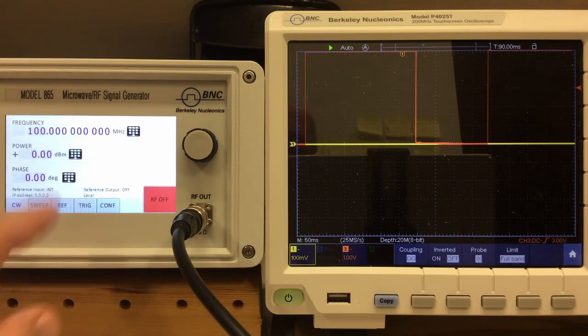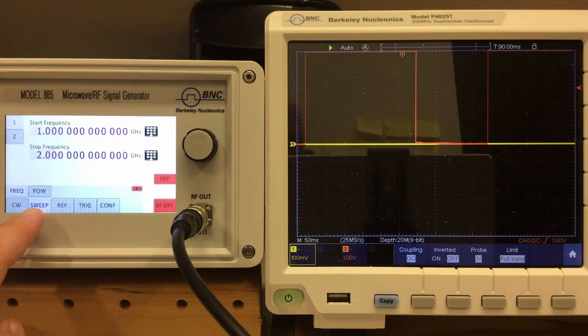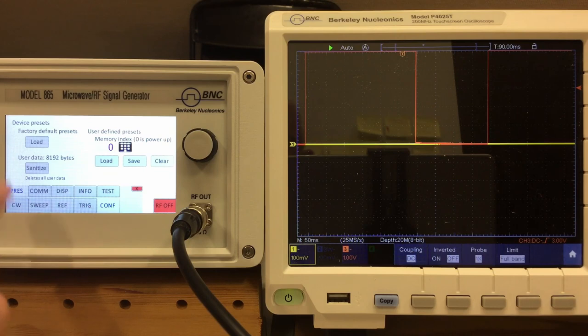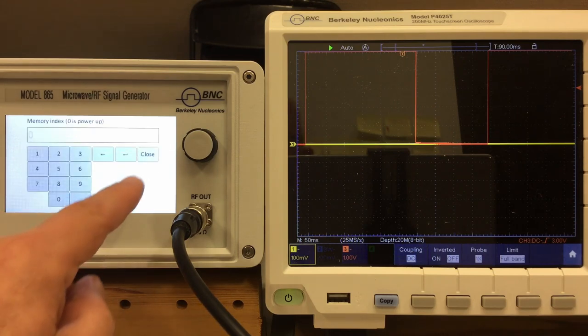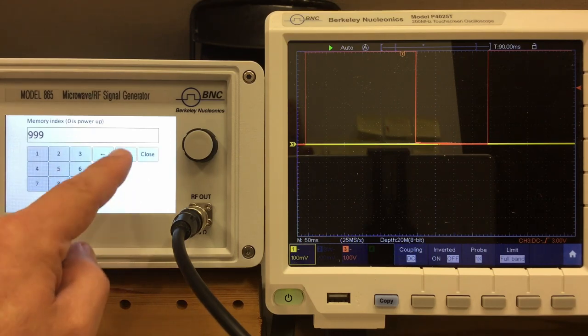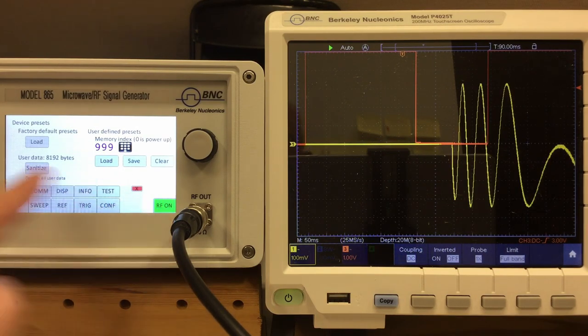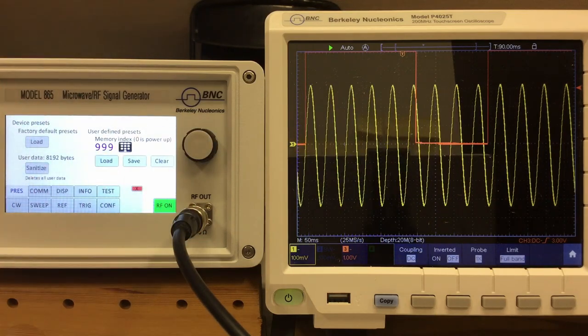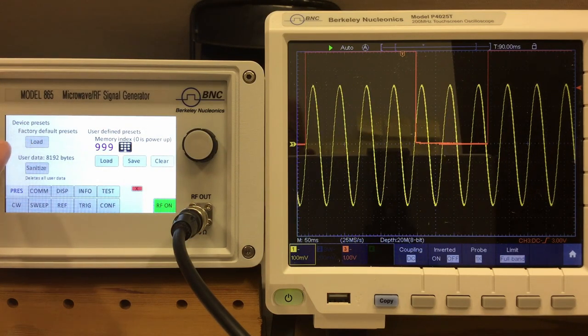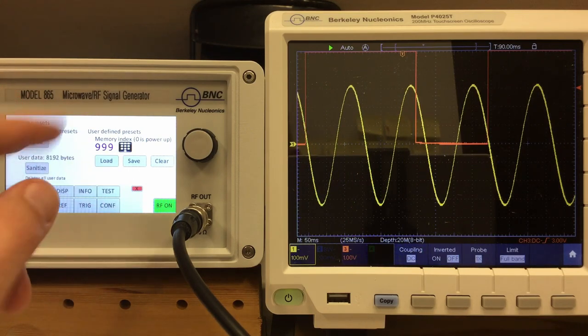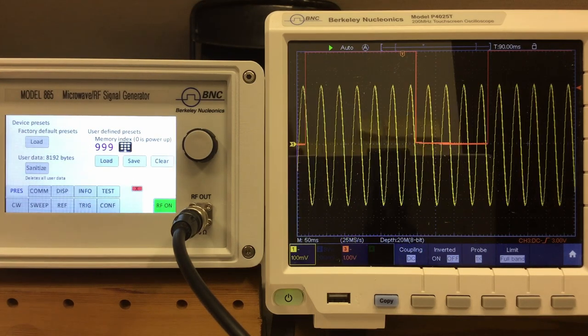Our sweep is gone, and our trigger is back to normal. But if I go to configuration, and then select setting nine nine nine, and say load, everything comes back on. And you can also load the factory defaults, and you can completely sanitize everything you have stored in memory.